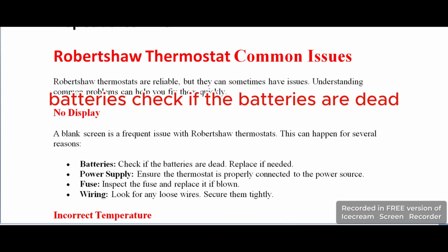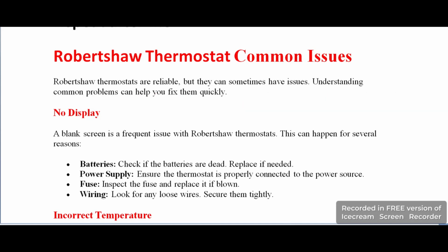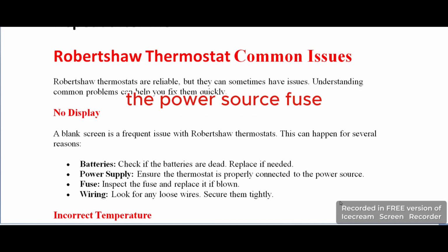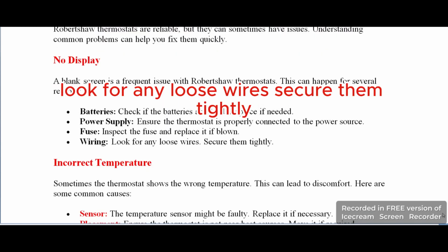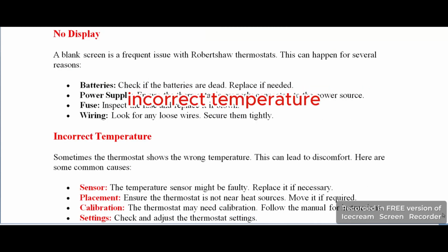Batteries. Check if the batteries are dead. Replace if needed. Power supply. Ensure the thermostat is properly connected to the power source. Fuse. Inspect the fuse and replace it if blown. Wiring. Look for any loose wires. Secure them tightly.